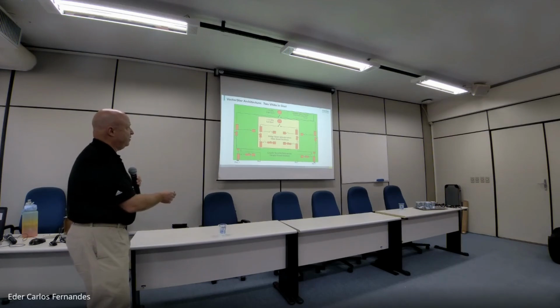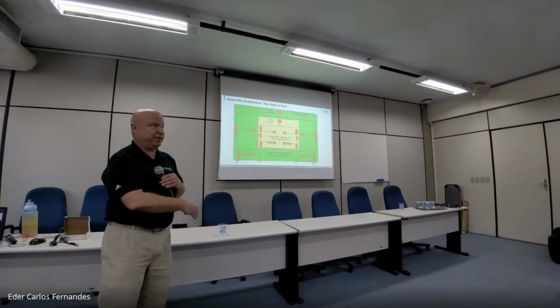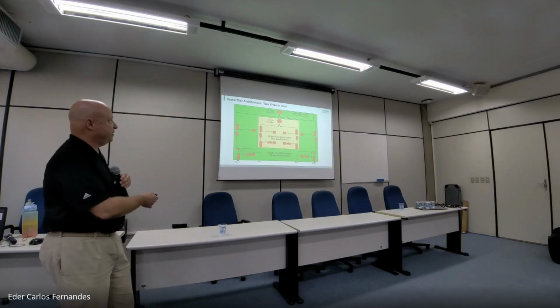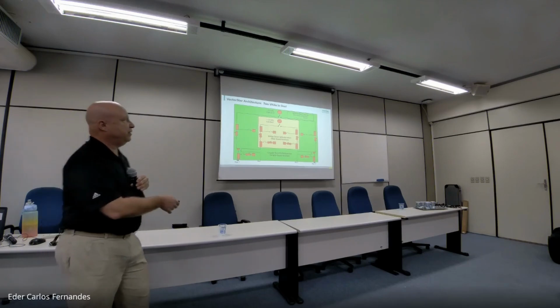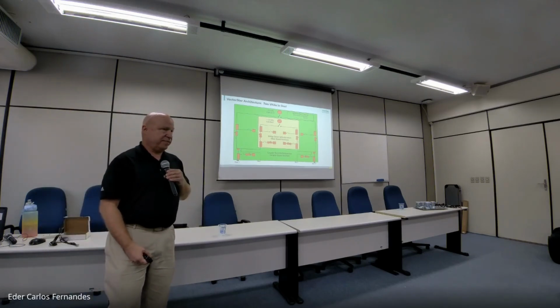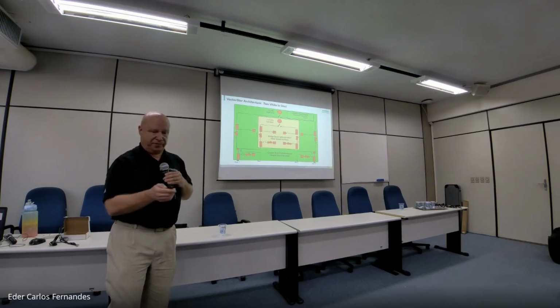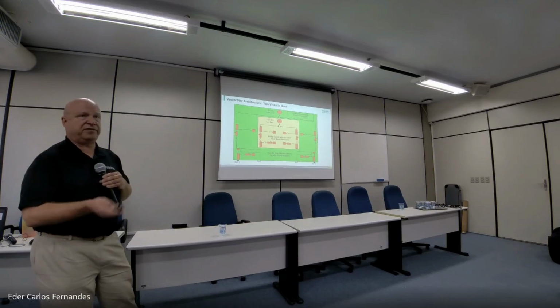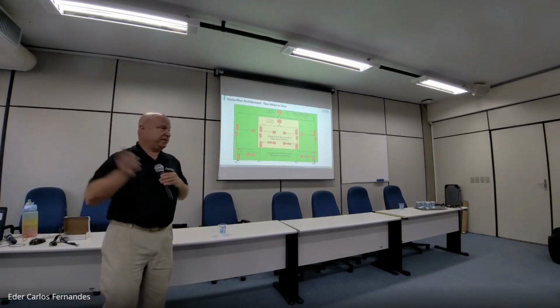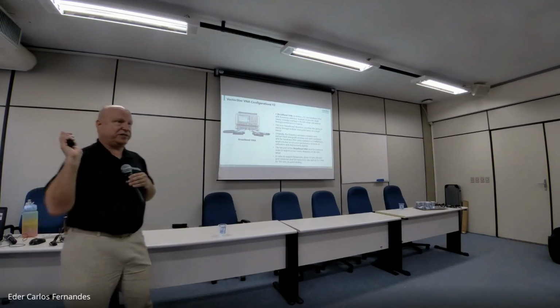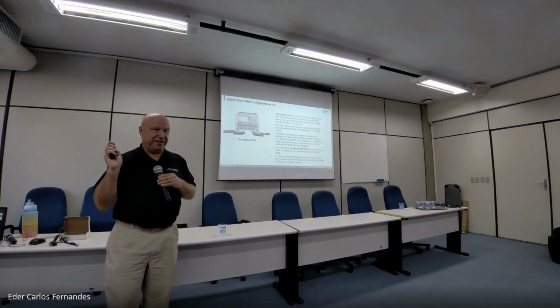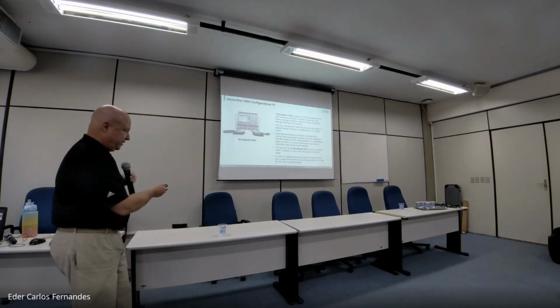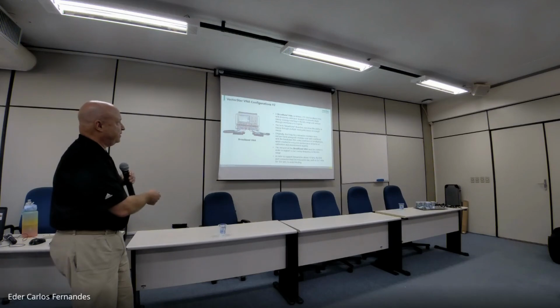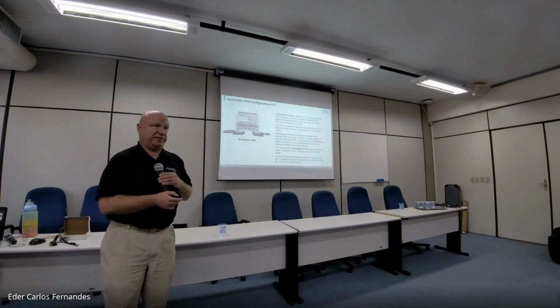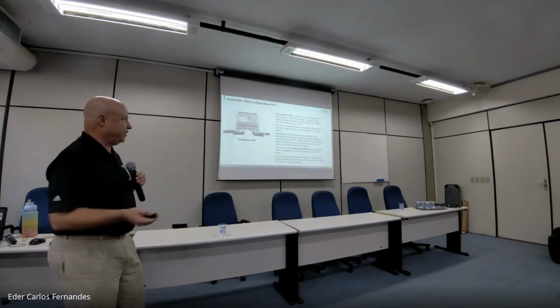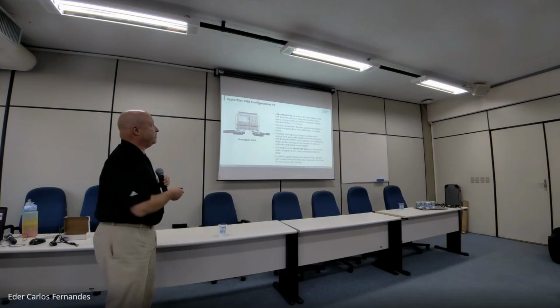So the low band here is everything below 2.5 gigahertz down to 70 kilohertz, and everything above 2.5 gigahertz is in the high band and utilizes more traditional microwave VNA architectures. But on a block diagram level, they look the same. It's just the components that are different. But it's what allows us to combine the 2 bands into one and go from 70 kilohertz all the way up to 70 gigahertz. But again, that was still the mainframe or the baseband VNA. Now we're going to take it a step further by adding the millimeter wave broadband test set that provides the interface to our frequency extenders and allows us to upgrade to 125, 145, and 220 gigahertz single sweep system.